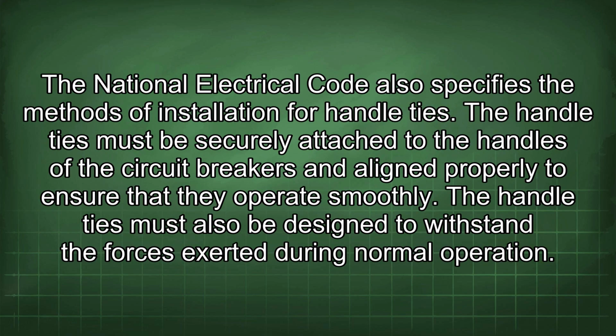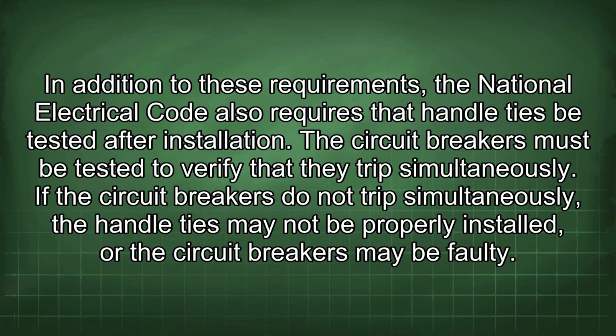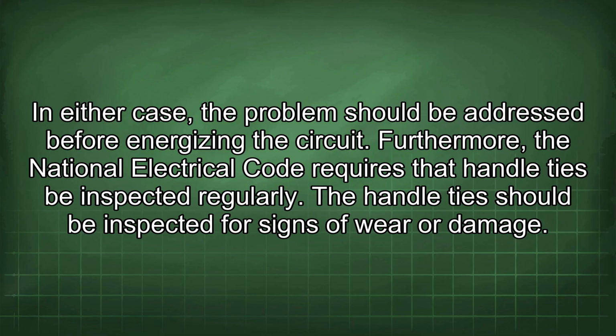The National Electrical Code also specifies the methods of installation for handle ties. The handle ties must be securely attached to the handles of the circuit breakers and aligned properly to ensure that they operate smoothly. The handle ties must also be designed to withstand the forces exerted during normal operation. In addition to these requirements, the National Electrical Code also requires that handle ties be tested after installation. The circuit breakers must be tested to verify that they trip simultaneously. If the circuit breakers do not trip simultaneously, the handle ties may not be properly installed, or the circuit breakers may be faulty. In either case, the problem should be addressed before energizing the circuit.